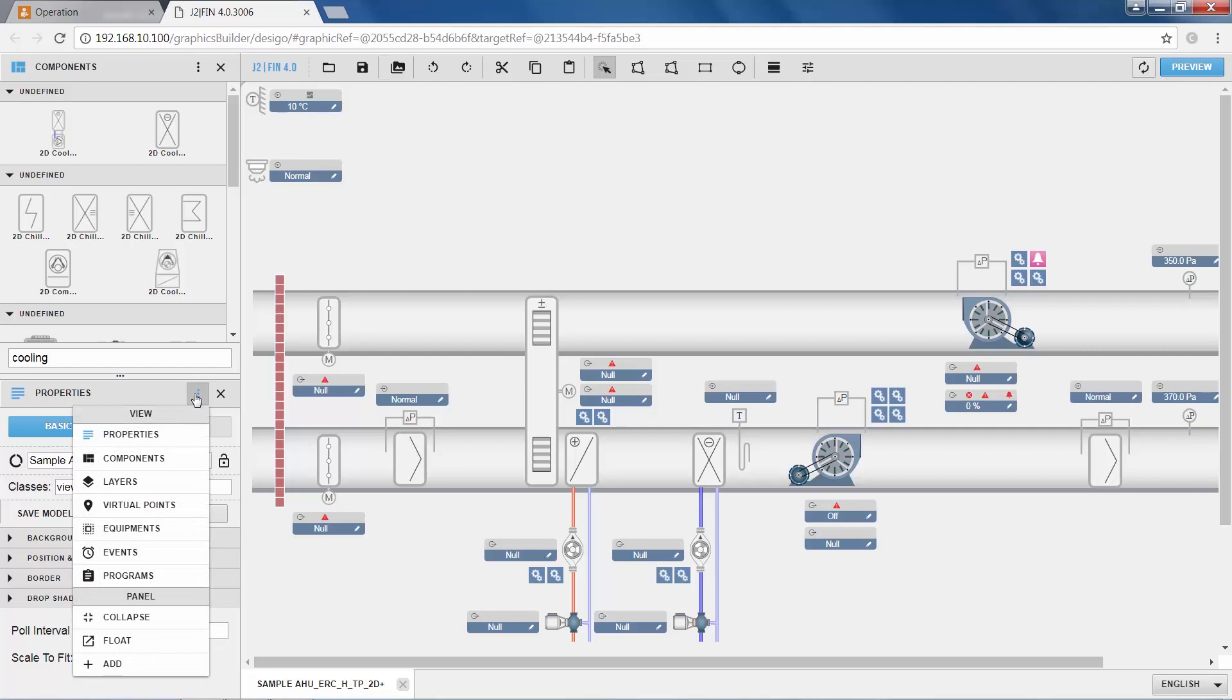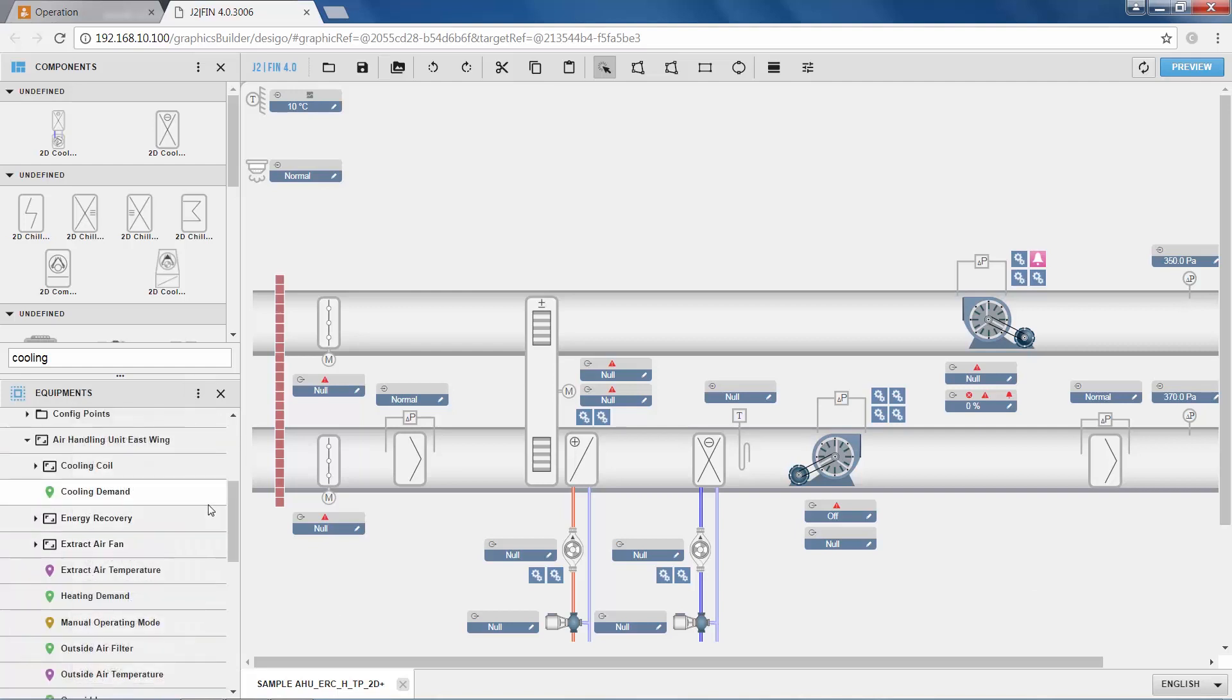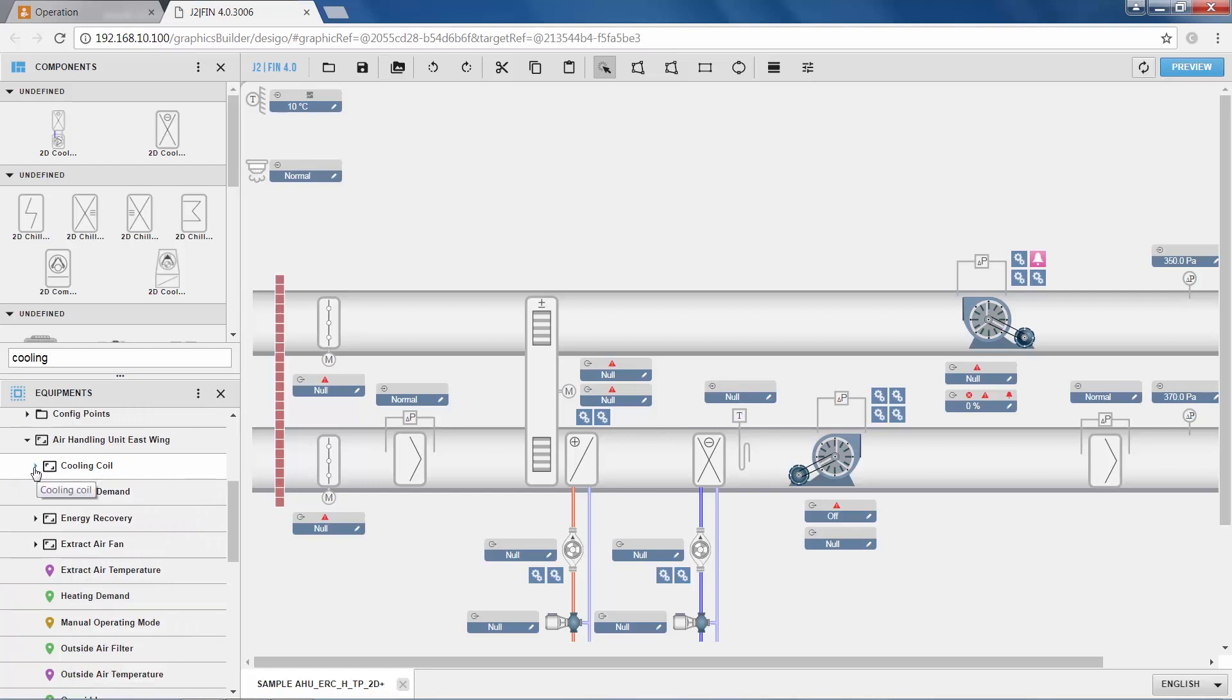And of course this cooling coil is now not connected to the automation data from the system yet. For this I move back to the points database. I look up the cooling coil in my data structure, and I can simply via drag-and-drop assign the points to its corresponding component.